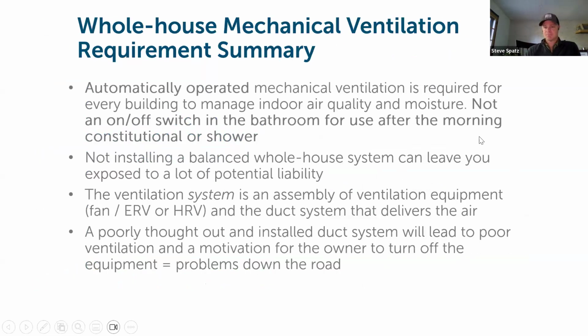So to sum this all up, what is required here is an automatically operated system that's going to be running either full-time, 24/7 continuously, or intermittently. One other thing I didn't show in detail in the REDCalc tool is that it can calculate for runtime. So you can put in parameters there if you're choosing not to have the system run continuously. You can define, if it's only going to run for X number of minutes per hour, what CFM would be required and how much that runtime needs to be. So that's another way to utilize that tool.